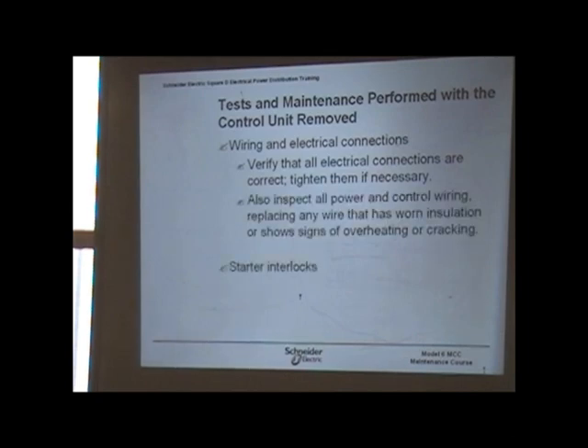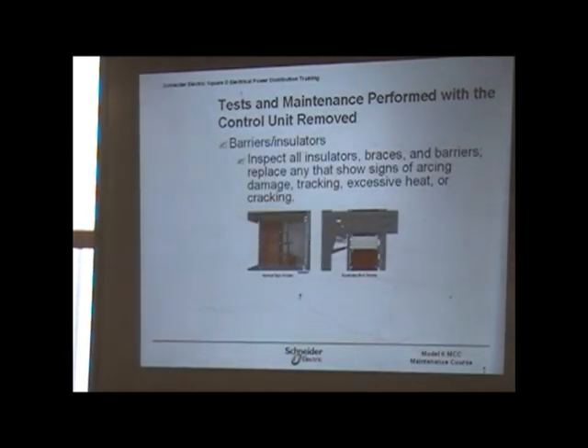We had an application down at one of the intakes. Normally your power comes in at the top of the breaker, loaded a lot of times - I don't like to use the word 'normally,' but a lot of the time. Well, this one, it came in from the bottom, where line became load and load became line. And it was 1,600 amps.